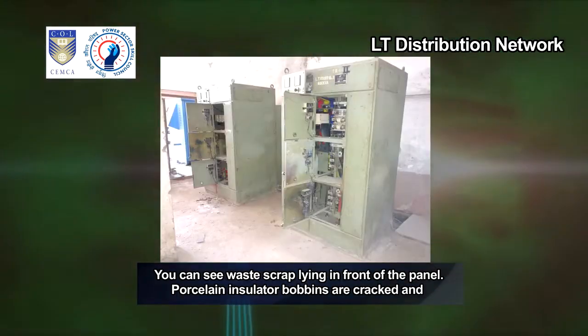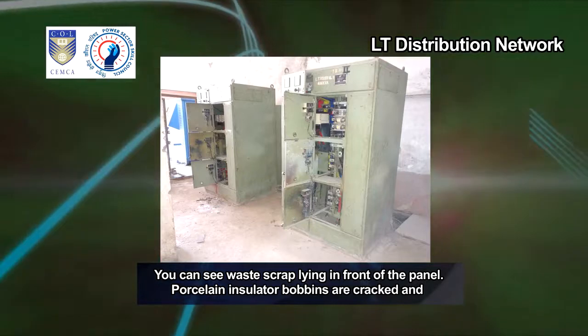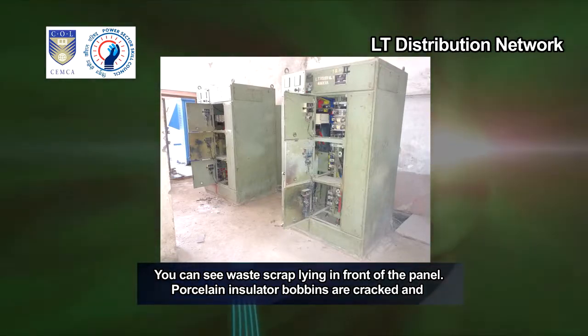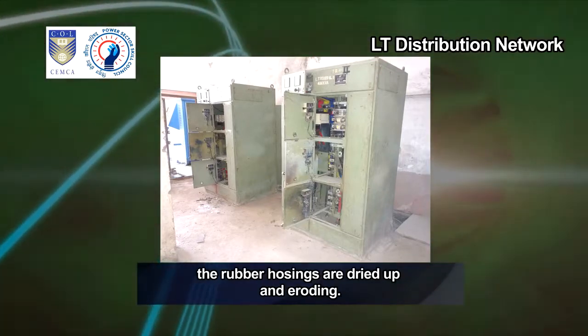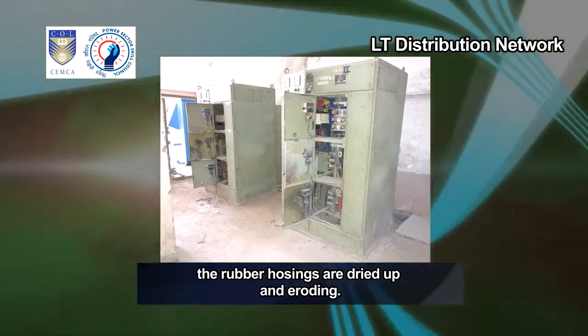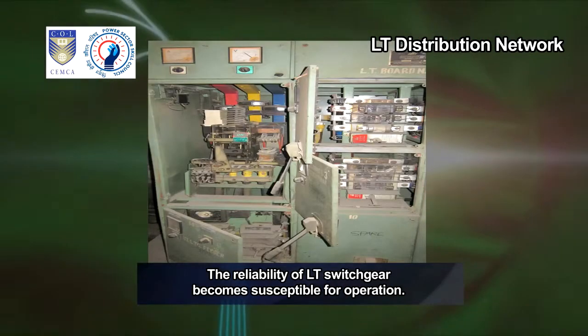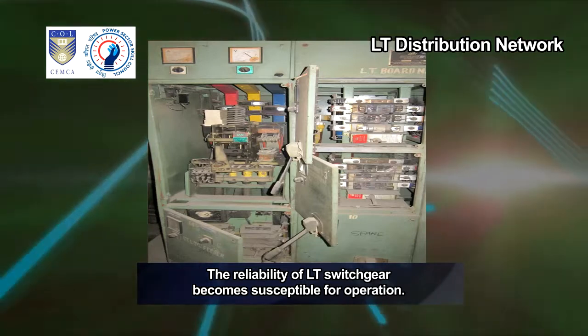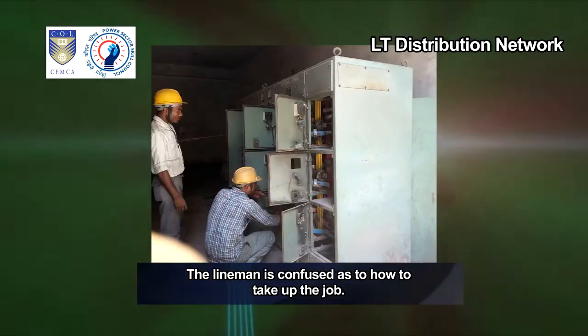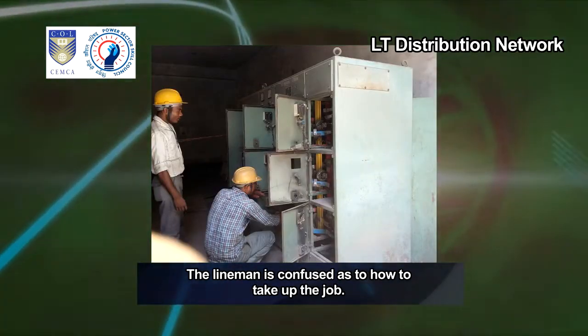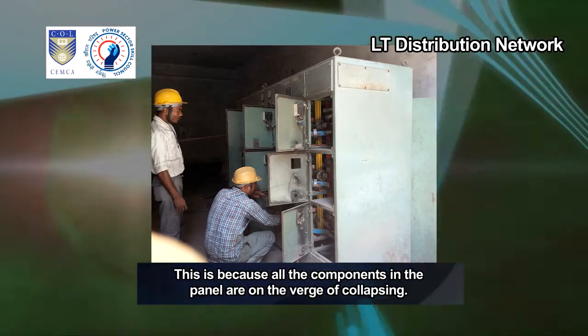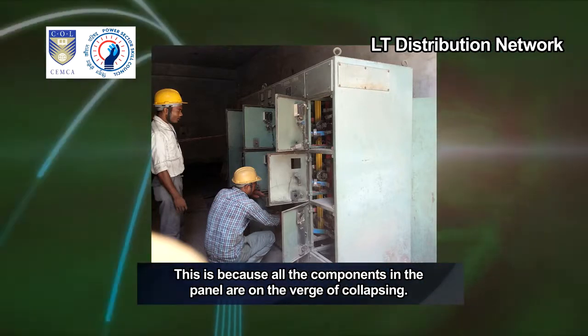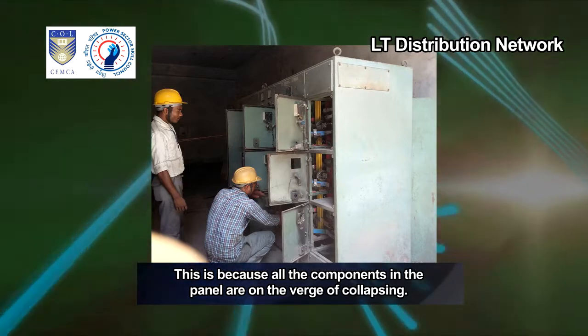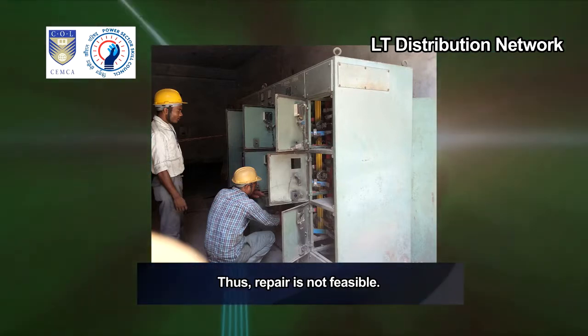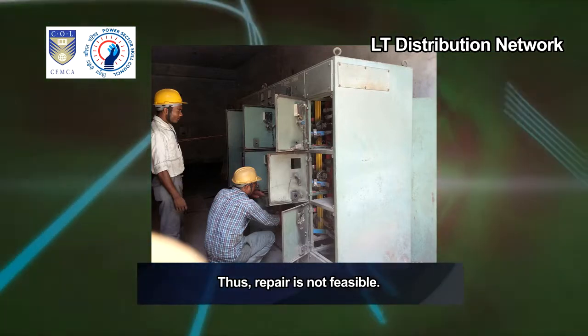You can see waste scrap lying in front of the panel. Porcelain insulator bobbins are cracked and the rubber housings are dried up and eroding. The reliability of the LT switchgear becomes susceptible for operation. The lineman is confused as to how to take up the job. This is because all the components in the panel are on the verge of collapsing. Thus, repair is not feasible.